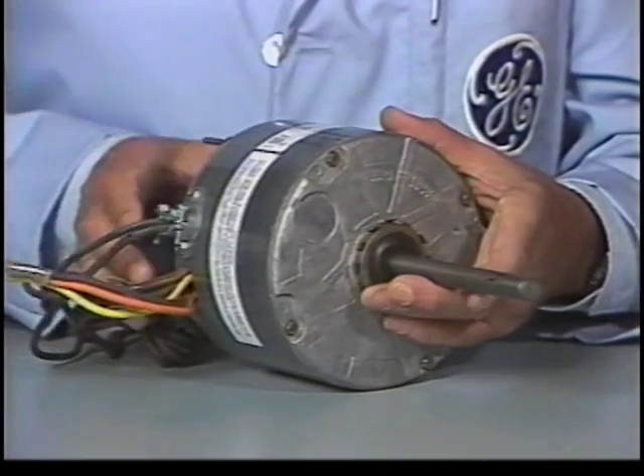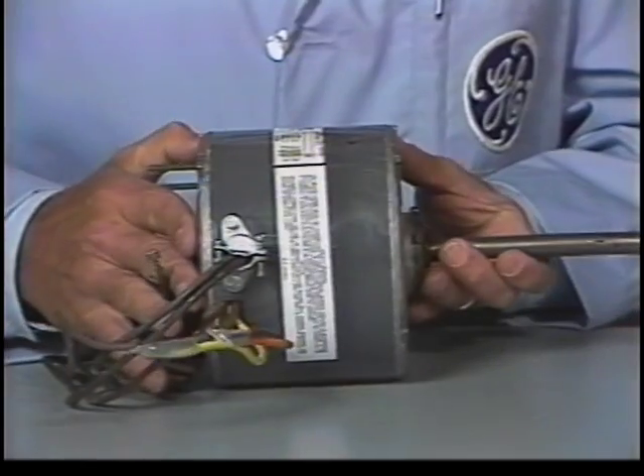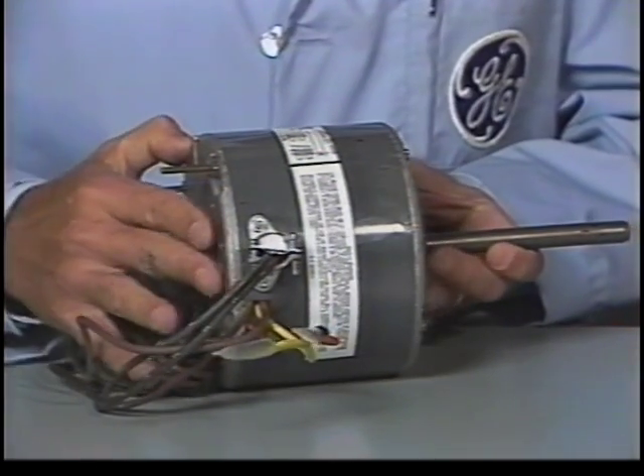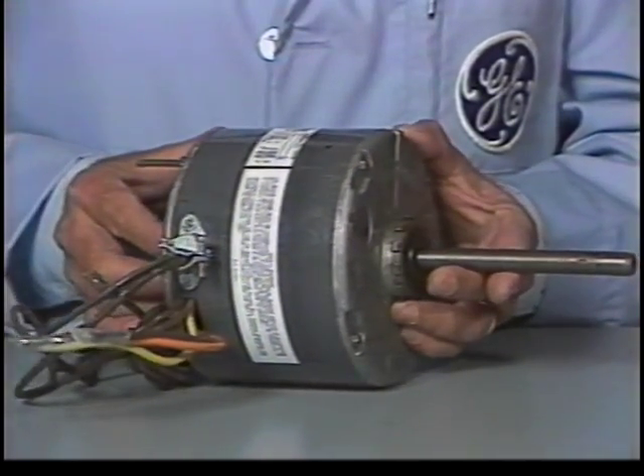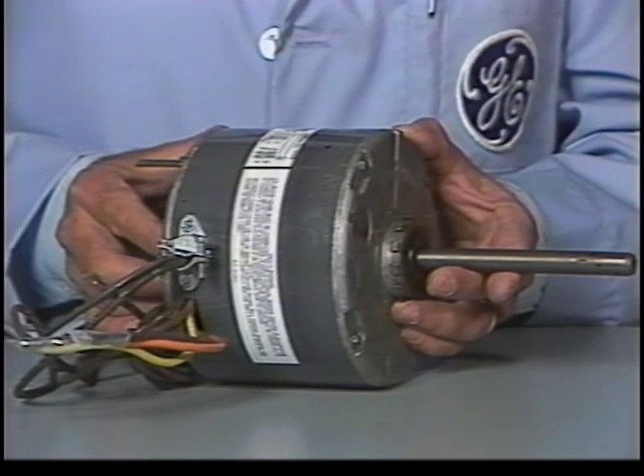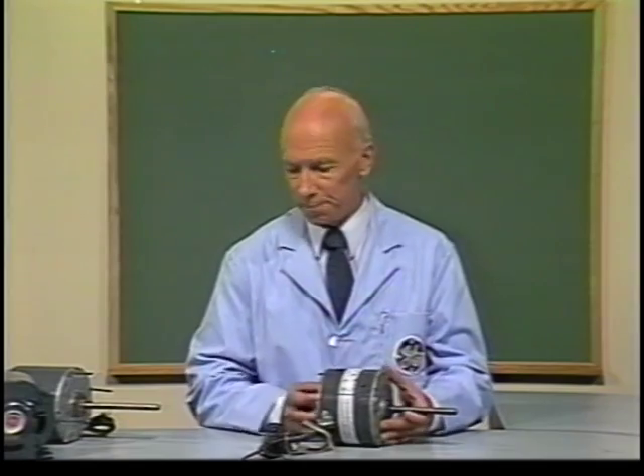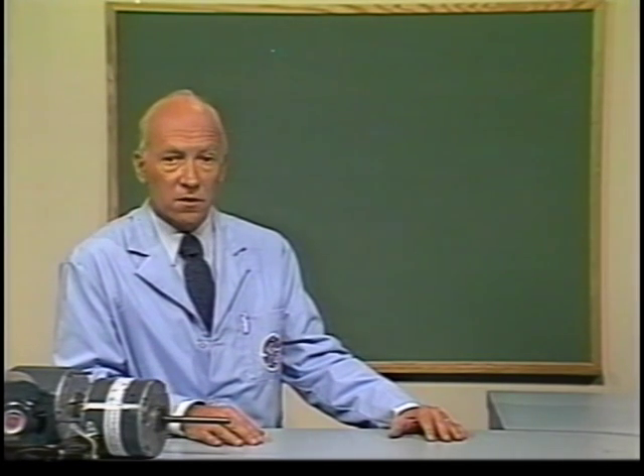The last common type of enclosure found on FHP motors is called totally enclosed non-ventilated. This enclosure protects the motor entirely from outside elements. Totally enclosed motors are normally larger than the same horsepower motors with open designs. The larger and more expensive design is needed to dissipate the heat since outside air does not reach the windings to cool them.